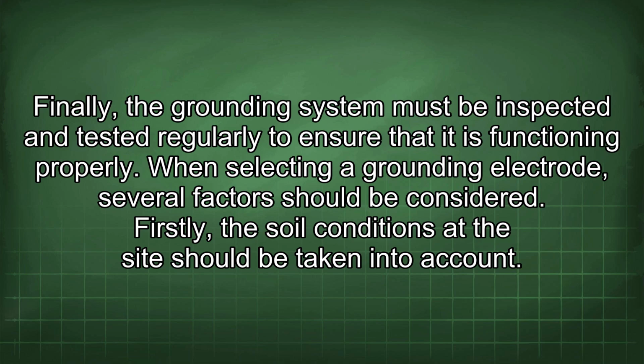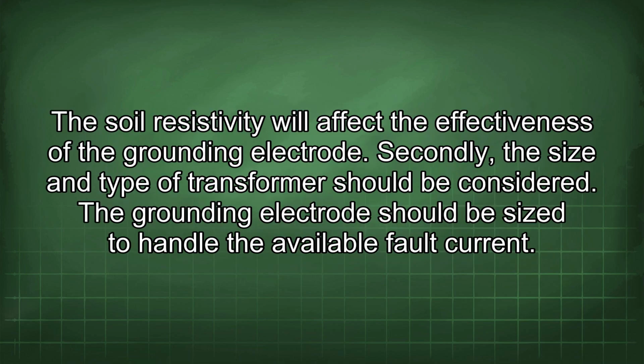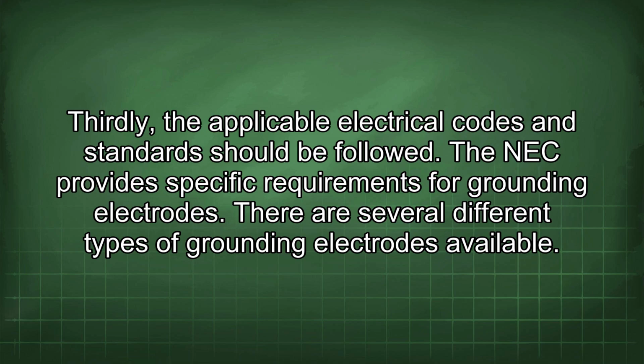When selecting a grounding electrode, several factors should be considered. Firstly, the soil conditions at the site should be taken into account. The soil resistivity will affect the effectiveness of the grounding electrode. Secondly, the size and type of transformer should be considered. The grounding electrode should be sized to handle the available fault current. Thirdly, the applicable electrical codes and standards should be followed. The NEC provides specific requirements for grounding electrodes.